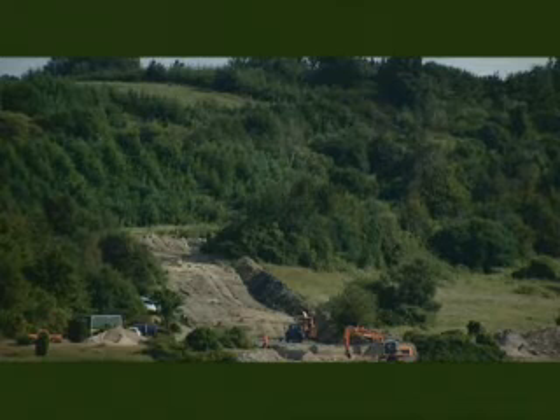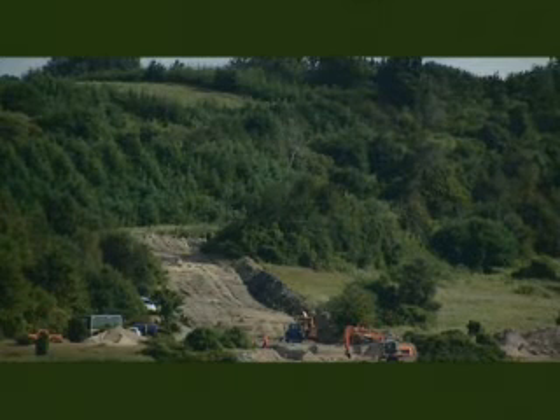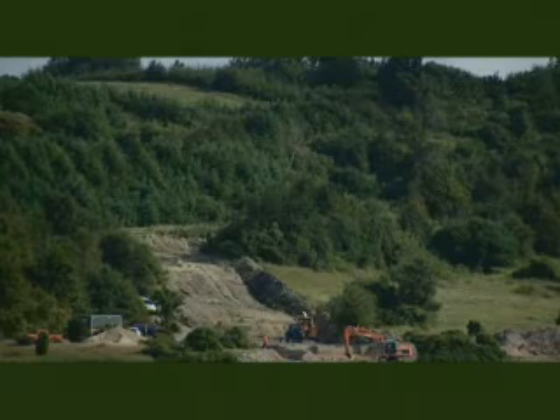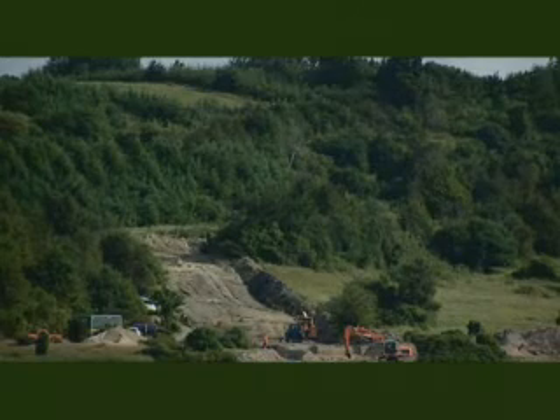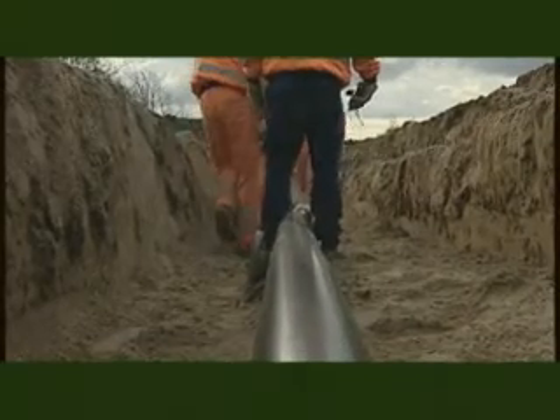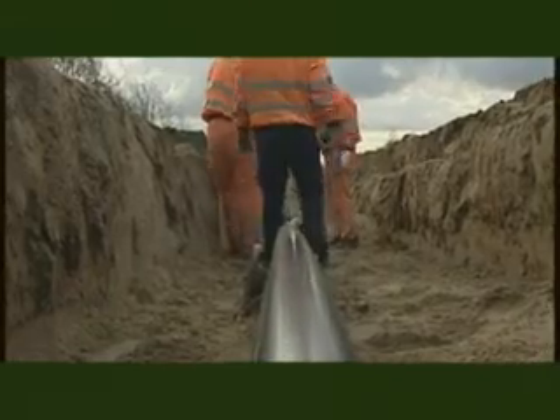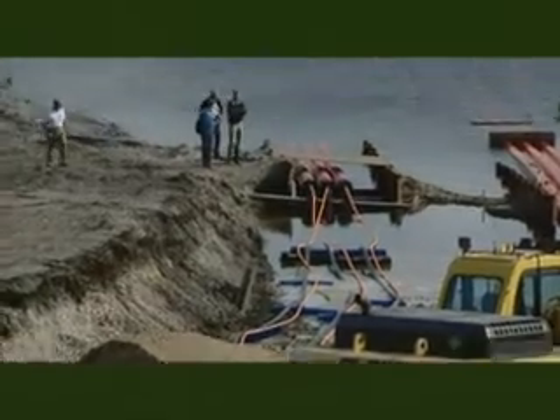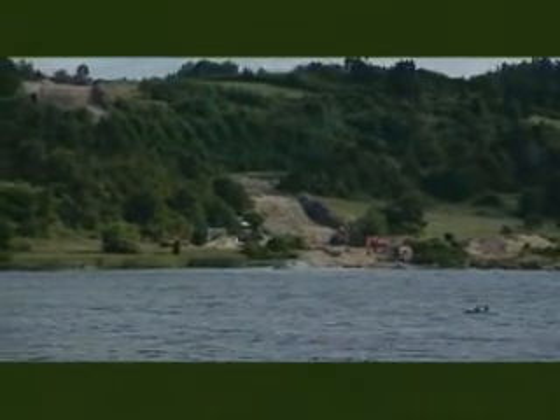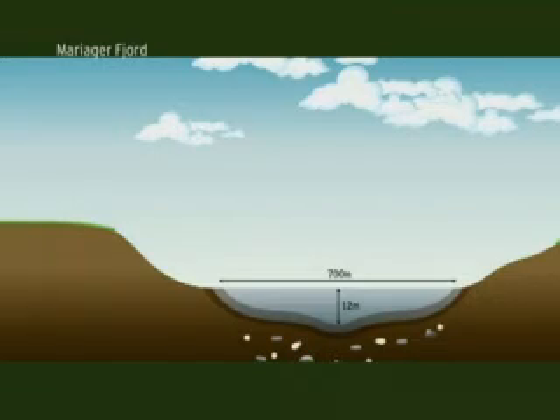On the northern side of the inlet, individual directional drillings have been made, traversing a slope and crossing a road. Elsewhere, the cables have been laid in open trenches. Crossing the inlet is a chapter in itself. At the crossing point, the inlet is about 700 metres wide. The maximum depth of water is only 12 metres.